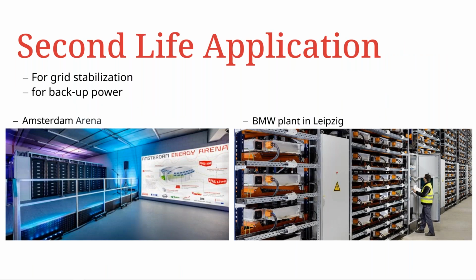Second life applications are primarily used for grid stabilization or backup power. For grid stabilization, an example is the Amsterdam Arena, which helps stabilize the available grid—not for a grid outage, but to help stabilize the active grid. If they notice a high shift in power availability, they can use these batteries to stabilize the grid. For backup, this refers to a sudden loss of full grid capacity, where you rely on the batteries to sustain your utilization of power.